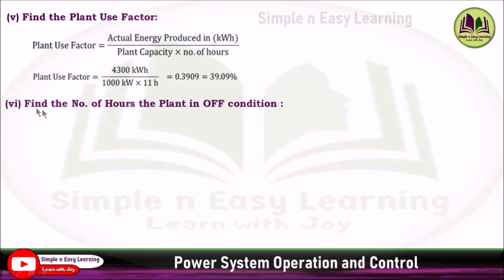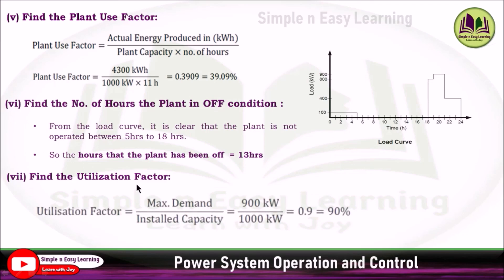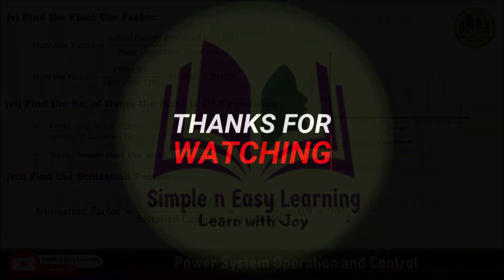Find the number of hours the plant is in off condition. Out of 24 hours, 11 hours the plant is used, so the remaining 13 hours the plant is in off condition. Find the utilization factor. Utilization factor equals maximum demand divided by installed capacity: 900 kilowatt divided by 1000 kilowatt, giving 90%.